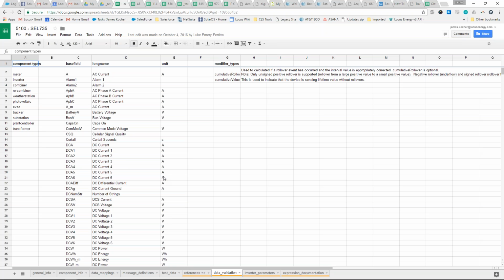Yep. And in most cases, it's one-to-one. One index will be used for a particular base field, but sometimes there are additions. For AC energy in particular, there's logic to look at a particular index value or register on the Aqua Suite and then take the difference every 5 minutes. That's how we get that nice curve, and it's not just a constant graph going up. So just keep that in mind. For certain base fields, there's additional math involved, but most of the time you just look at what is in these data mappings columns, and it'll tell you which registers go to which names in the platform.